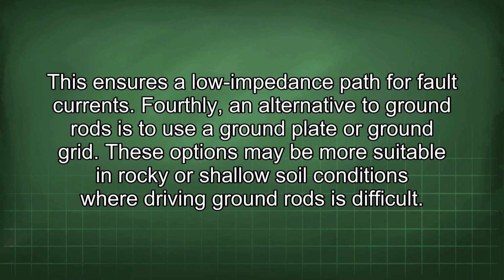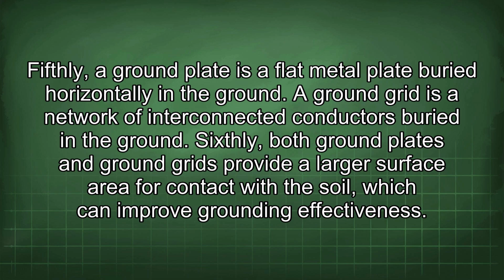Fourthly, an alternative to ground rods is to use a ground plate or ground grid. These options may be more suitable in rocky or shallow soil conditions where driving ground rods is difficult. Fifthly, a ground plate is a flat metal plate buried horizontally in the ground. A ground grid is a network of interconnected conductors buried in the ground.